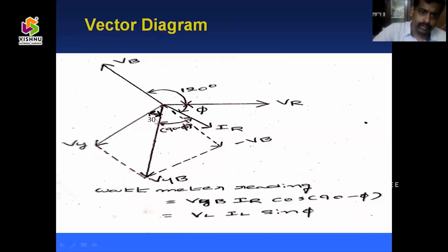If you subtract 30 degrees from 120 degrees, you will get the phase angle between VYB and VR. That is nothing but 90 degrees. And if you subtract phi from 90, you will get the phase angle between VYB and IR. So like this, we can find the phase angle between VYB and IR. Once you find it, we can easily understand that the wattmeter reading is nothing but the reactive power.